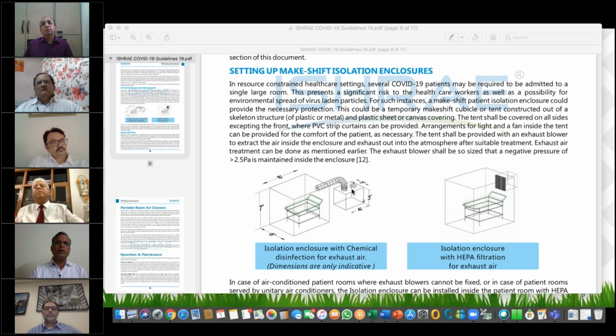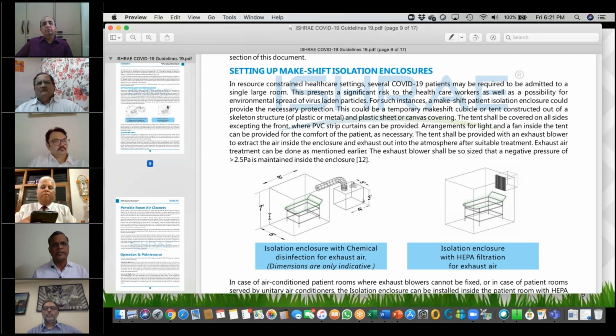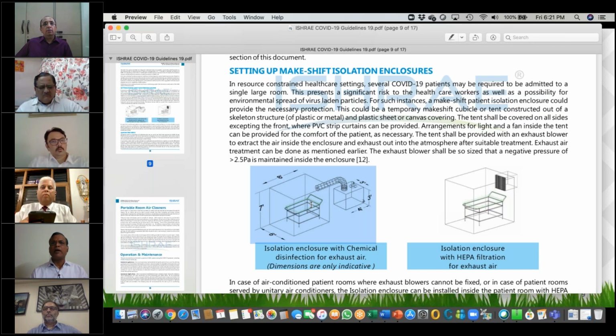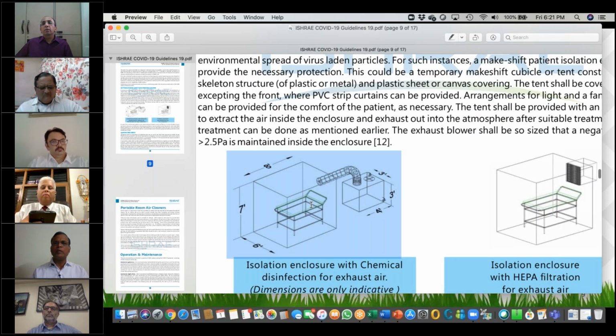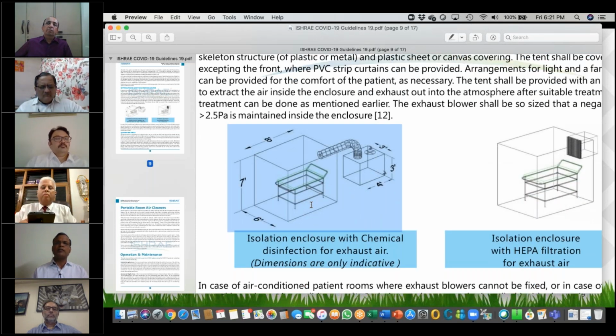The makeshift enclosure is typically plastic or aluminium framework with transparent acrylic sheets, so the patient can be monitored from outside. This gives physical segregation, but since you cannot make it airtight, and particles are submicronic, they drift around by diffusion and tend to come out of the enclosure. That's why we suggest maintaining negative pressure with constant airflow from the room into the enclosure.